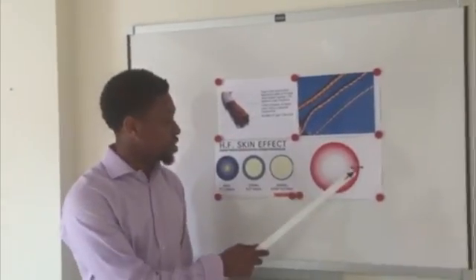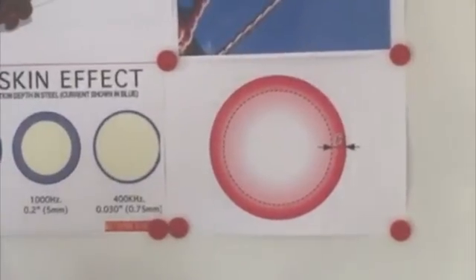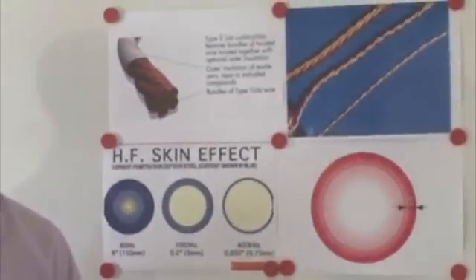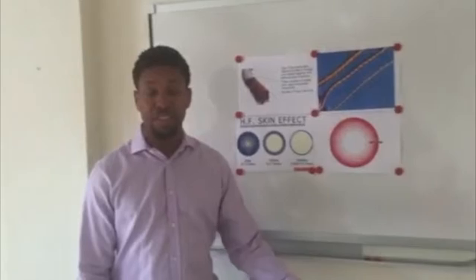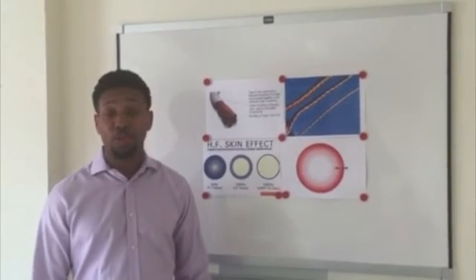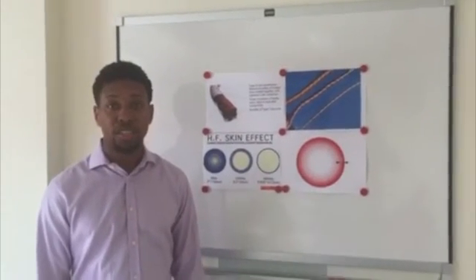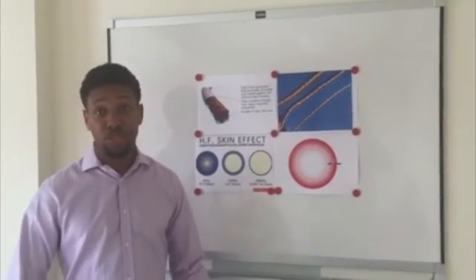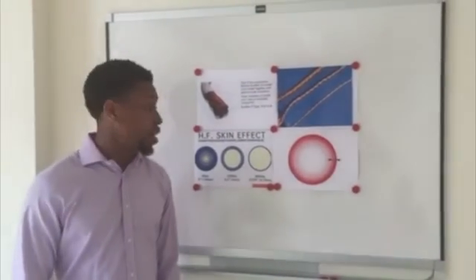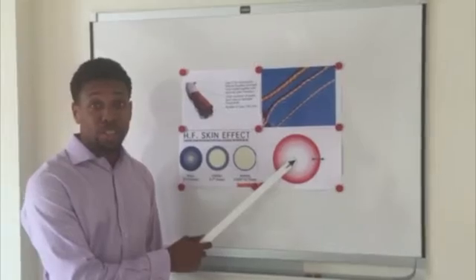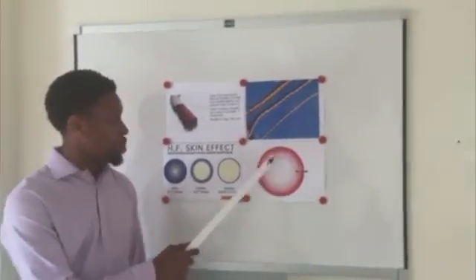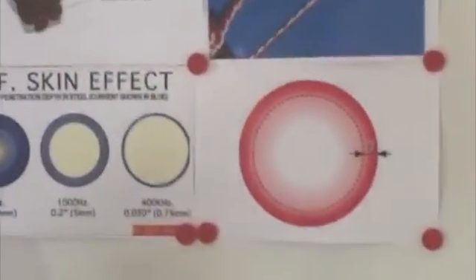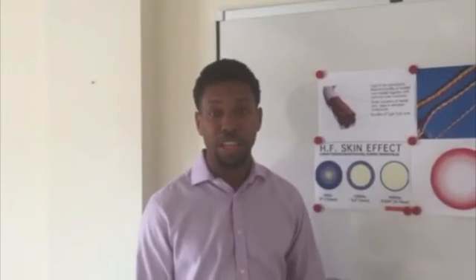What we have here, the delta represents the skin depth. This is the depth carrying the majority of the current, and this is what we want to increase to reduce the effect of the skin effect. This phenomena is more prevalent within larger conductors, so there are several methods we could use just within this vein. Having a hollow cross-section reduces the amount of wasted material, as you have the area in the center, which isn't carrying much current, missing, and so you have less weight and less expense on your overhead line.